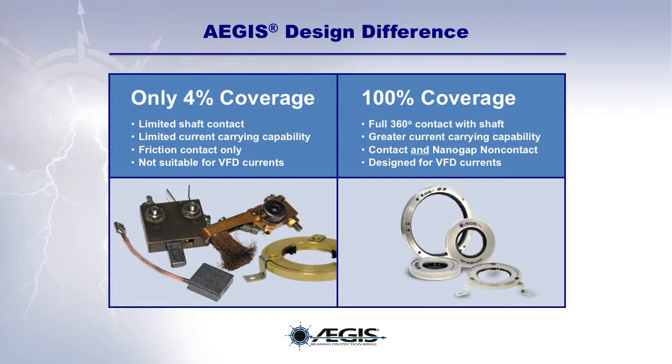Where single point or discrete point grounding brushes provide only about 4% coverage of the circumference of the motor shaft, AEGIS rings provide 100% coverage. This is because the conductive microfibers of the AEGIS ring completely surround the motor shaft, providing full 360-degree contact with the shaft.